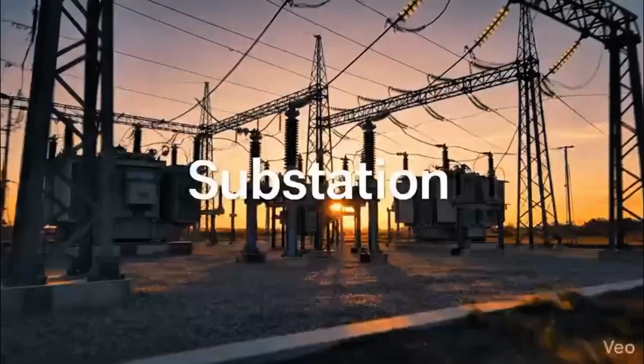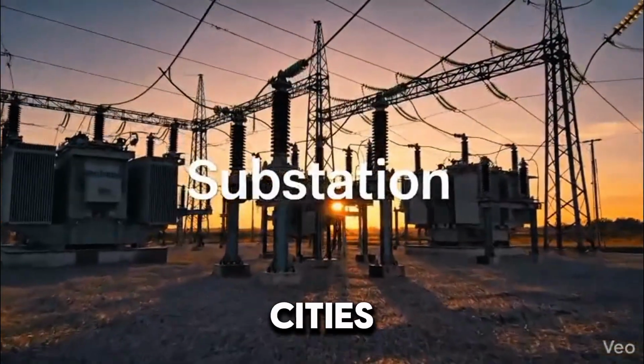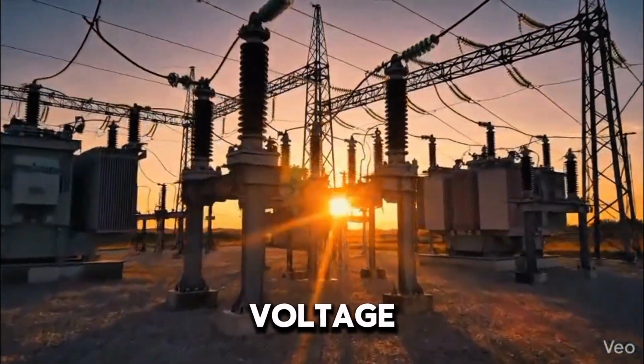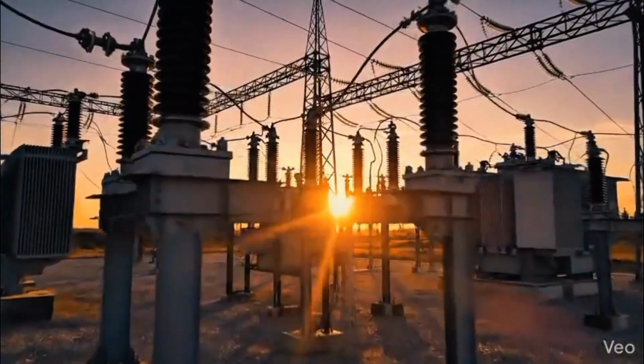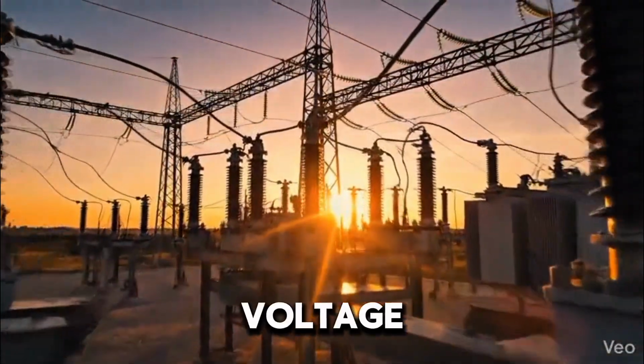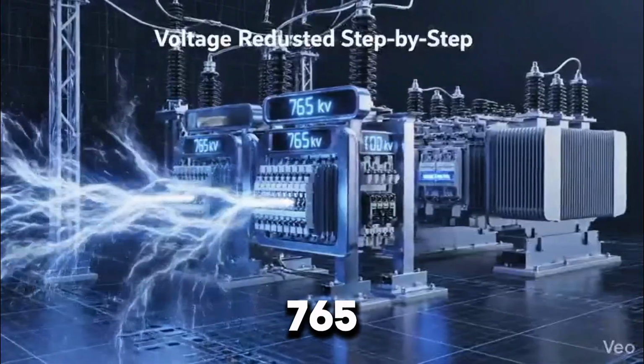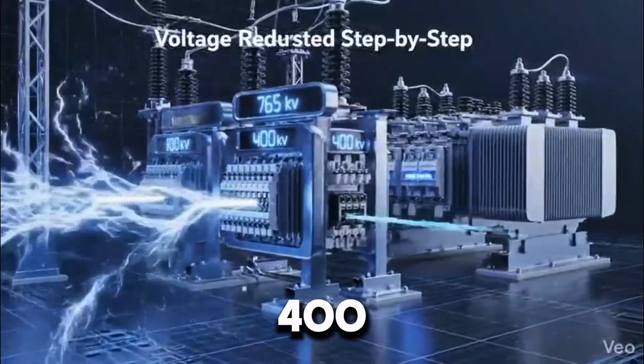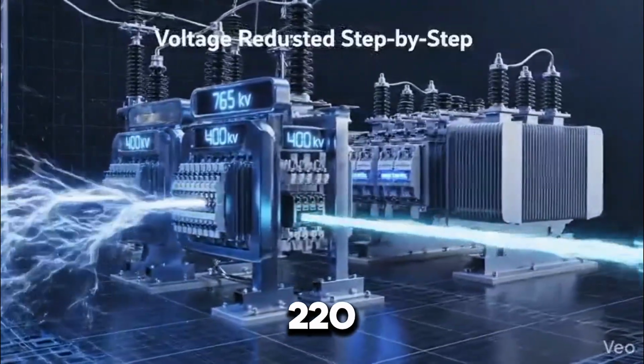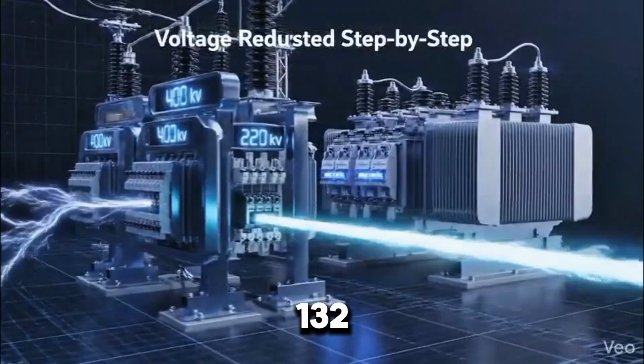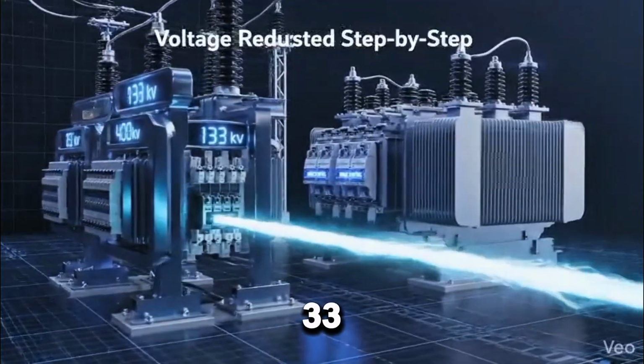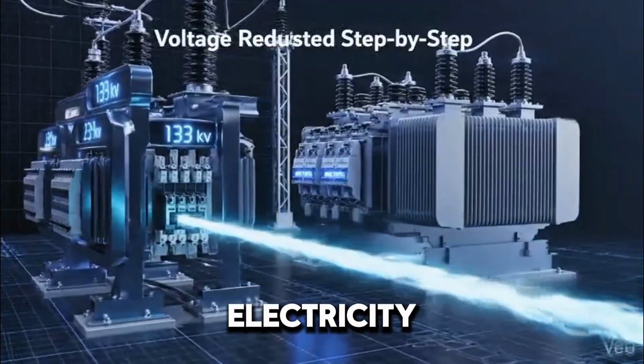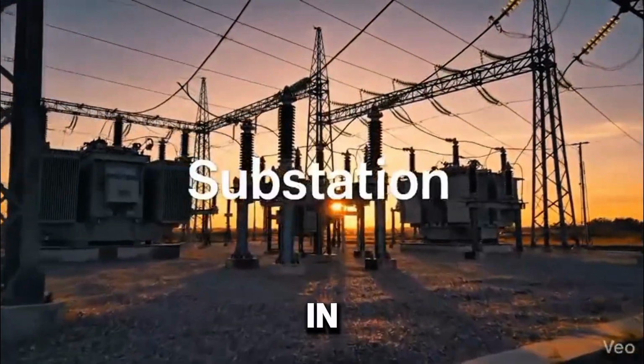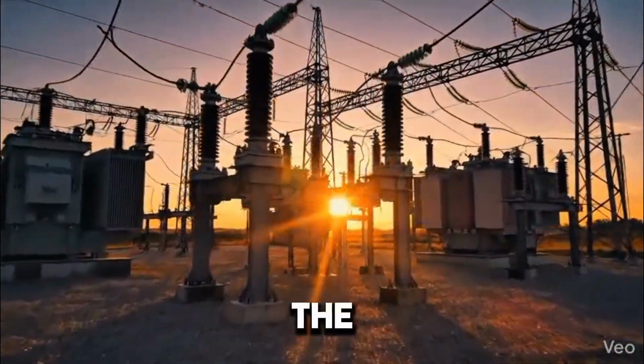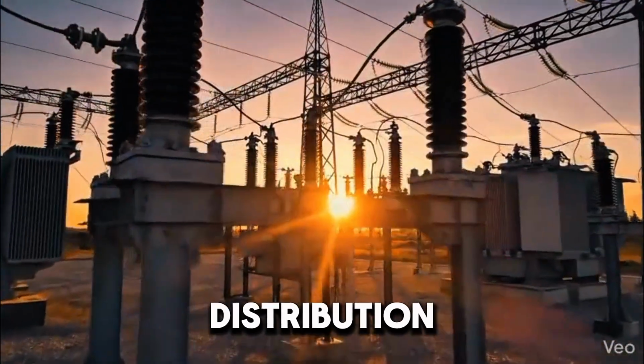Substations: as electricity approaches cities, it cannot be used at such high voltage, so it enters a substation. Here, the voltage is reduced step by step, from 765 kilovolts to 400 kilovolts, to 220 kilovolts, to 132 kilovolts, and then to 33 kilovolts. Each stage makes electricity safer and more usable. Substations also play a critical role in controlling power flow, protecting the system, and managing distribution.